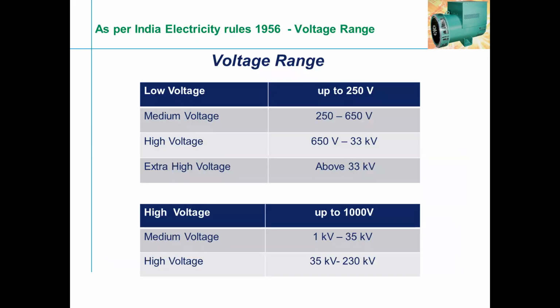Coming to India, I'm just covering India. In India, the voltage levels are classified as low voltage up to 250 volts, medium voltage 250 to 650 volts, high voltage 650 volts to 33 kV, and extra high voltage above 33 kV. So these are the fundamentals of our voltage requirement, where the electricity board of India supplies the grid. So we, as a generator manufacturer, have to give a supply in line with the system requirement, whether it is domestic, commercial, or industrial.